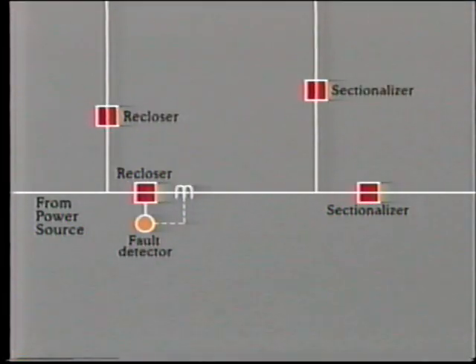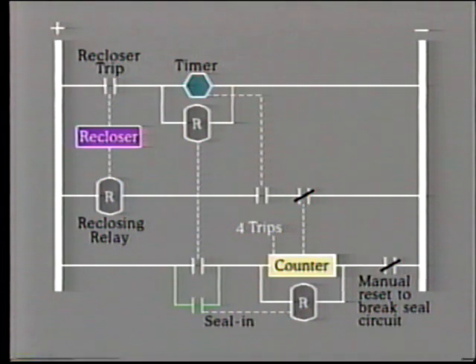Let's now look at the arrangement for a recloser. Here, the recloser trips on high current and recloses after a time interval of, say, 10 seconds. The idea is to allow a temporary fault such as lightning to clear during this time delay. The recloser is allowed 3 reclosures before finally locking out in the tripped position. This control circuit shows the arrangement.